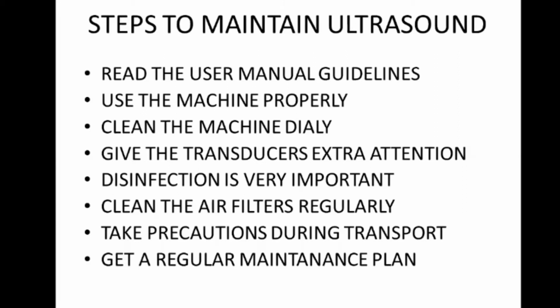Then the third point is clean the machine daily. As I said, I explained to you yesterday and the day before yesterday also, probes play a major role here. You have to clean the probes, keyboards and the trackball on a regular basis with tissue. Sometimes dust goes inside and starts giving speckles in the image. It will start producing white lines, and then white dots in the image. These are things you can avoid if you clean the machine daily.